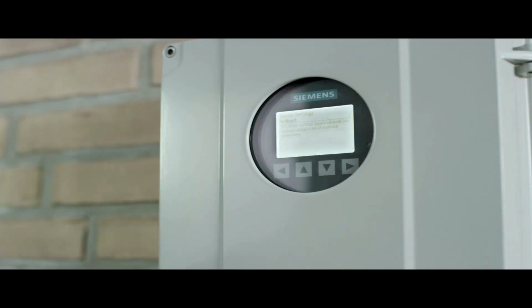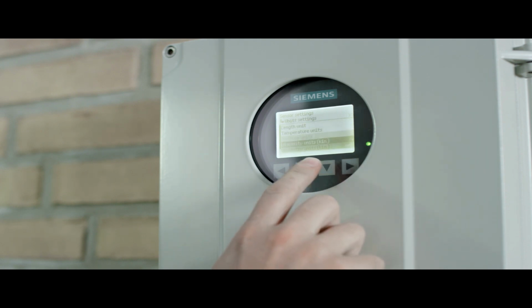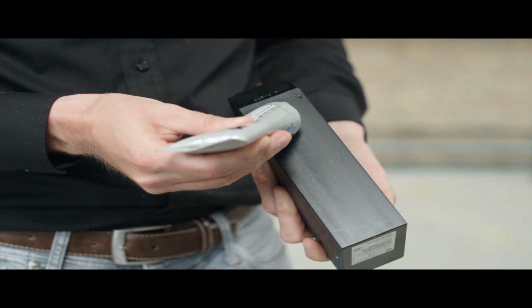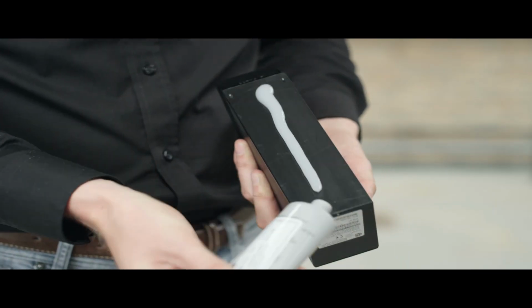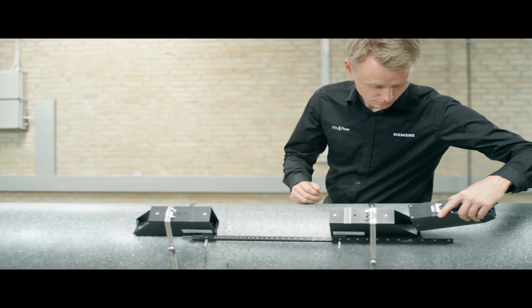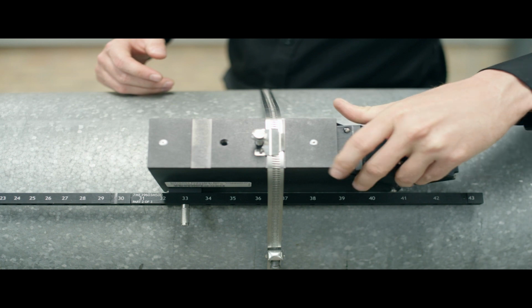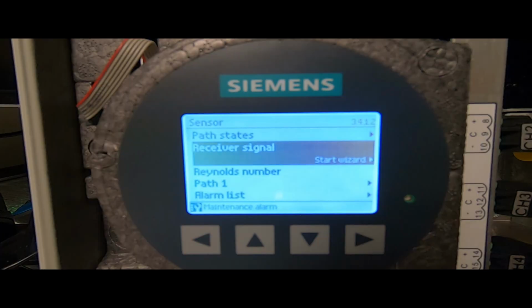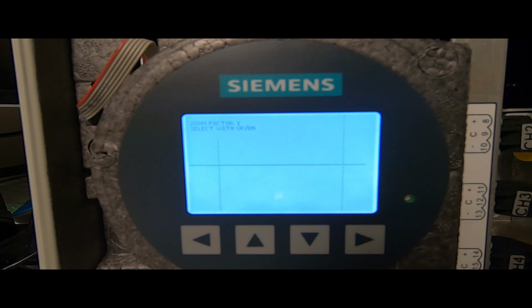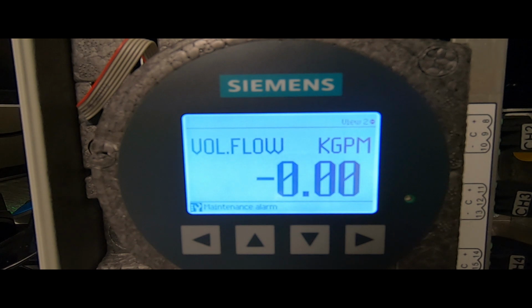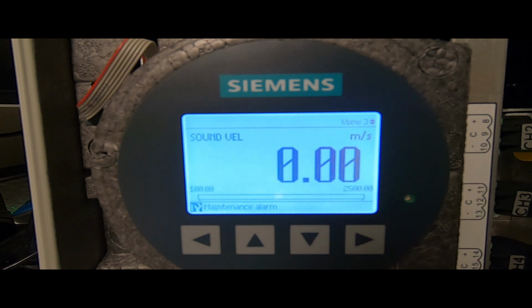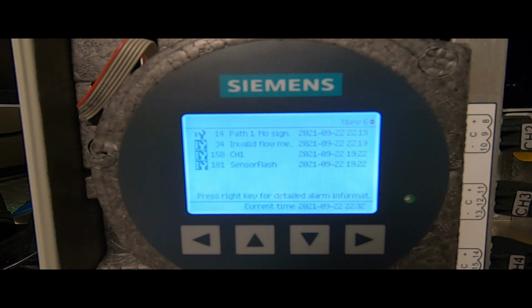You've installed your clamp-on flow meter, but can't seem to get it to work. You are careful to follow all instructions for programming accurate pipe dimensions, use of coupling material, and proper installation of the sensors at the spacing indicated by your flow meter. But your flow meter won't measure flow. Instead, your receiver signal is just a flat line. Your flow indication and sonic velocity measurements are showing zero values. And you also notice some active maintenance alarms. The bottom line is you have no ultrasonic signal.